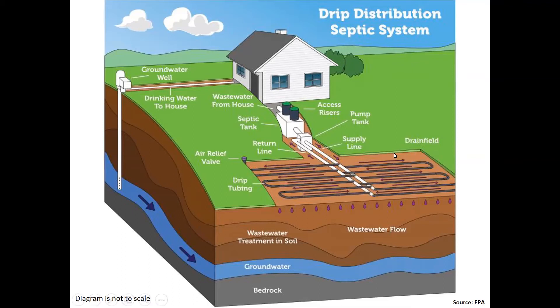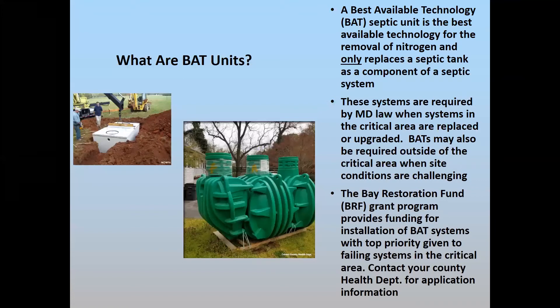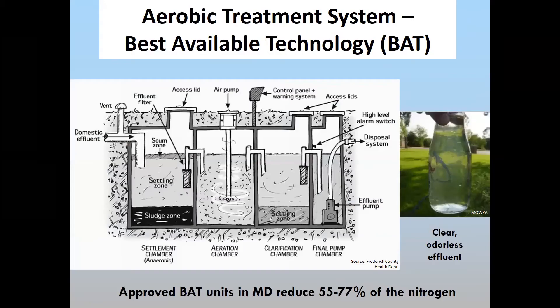Here's a drip system, where tubes are laid out to distribute the wastewater evenly over the entire soil treatment surface. These are typically placed about 6 to 12 inches below the surface of the soil. Then we have BAT units — another term is advanced treatment unit. In Maryland we use the term best available technology. You can see from this photo that this particular unit has three access ports located at the soil surface.